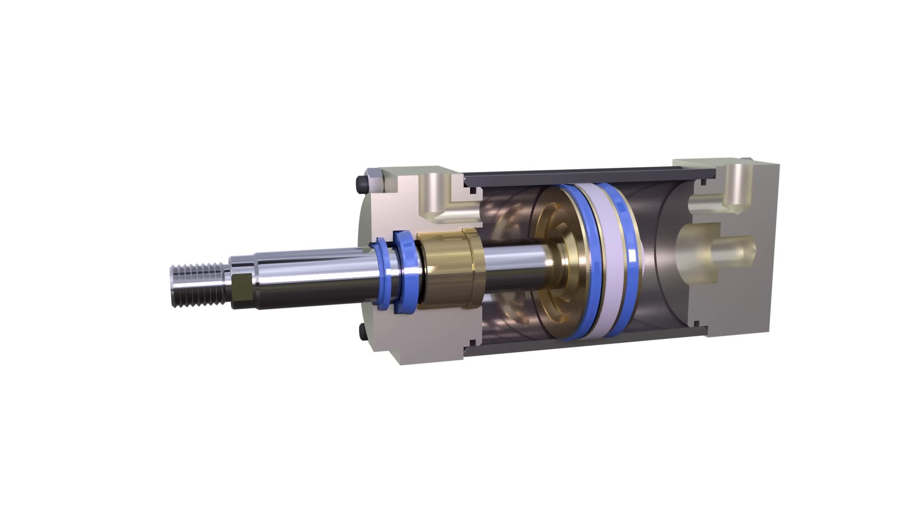What's inside a pneumatic cylinder? A cylinder piston is inside a cylinder barrel, a pipe with a smooth inner surface. The piston has seals for separating the piston and rod cavities. The piston may also have piston guide rings. They ensure the sliding of the piston along the cylinder barrel.